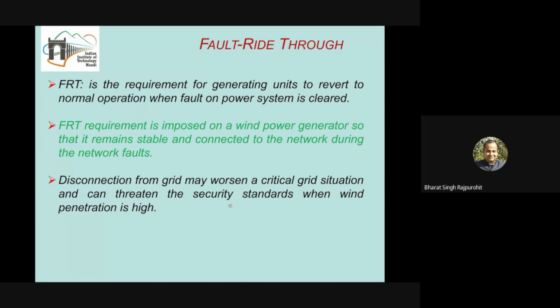Now the bigger capability we are able to see with the DFIG is fault ride-through, and let's see how we will be able to meet it. The basic meaning of fault ride-through is in two senses. The first sense is that the wind turbines should be able to defend against a fault for their own safeguard, as well as keep working during the fault and remain connected to the grid, so that they can provide active or reactive power to the grid. So this is the overall broad sense: making sure that the system is stable during the fault, as well as that the individual wind farm is safeguarded during the fault. Both of these ride-through capabilities are expected during the fault condition. Earlier, a simple disconnection was there, but now it is not expected.